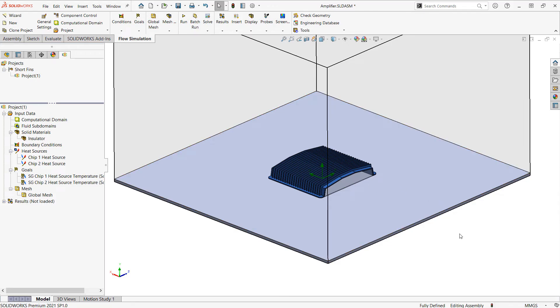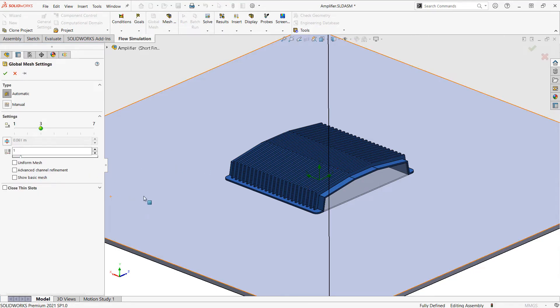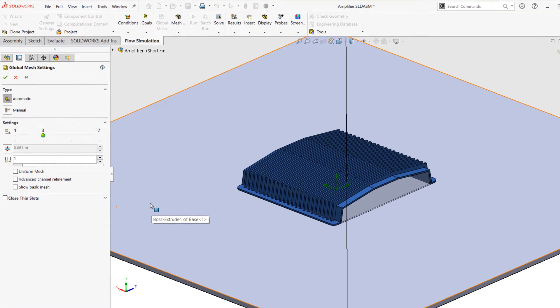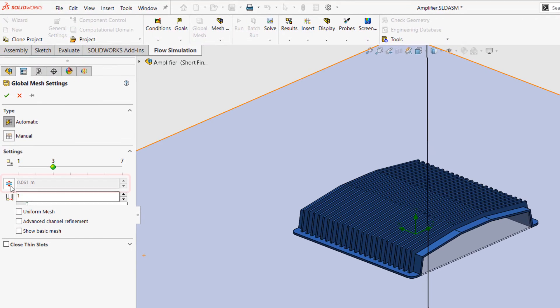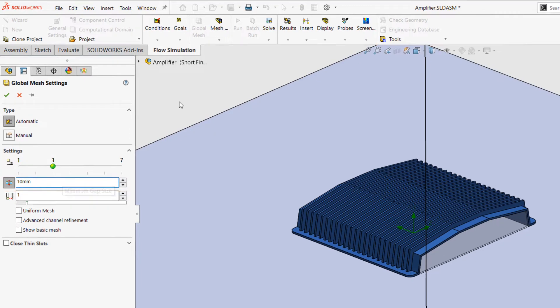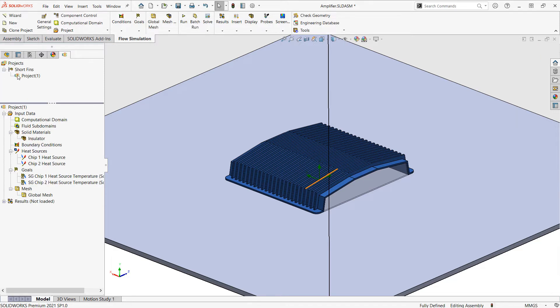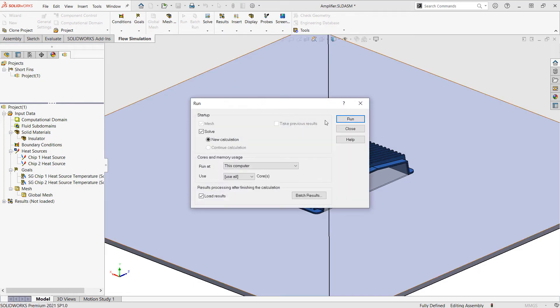Now I do want to pay a little bit of attention to the mesh this time so we're going to edit the global mesh and I'm going to enable this option for minimum gap size and type in a number of 10 millimeters, which is roughly the distance between the fins, to make sure we resolve that in our simulation. That should be all the setup I need so I can go ahead and run the analysis.